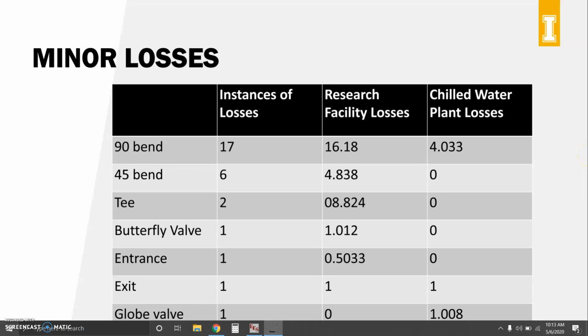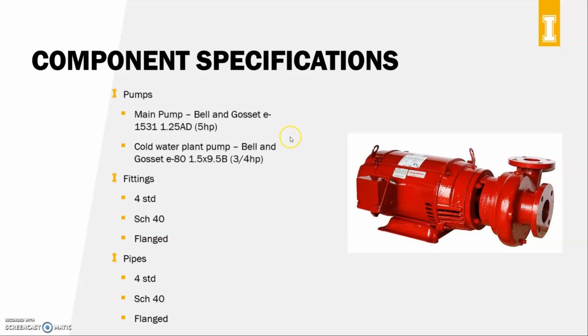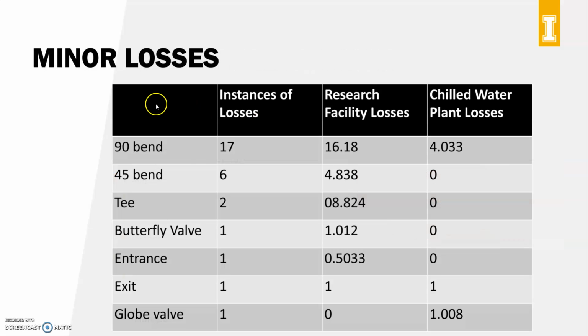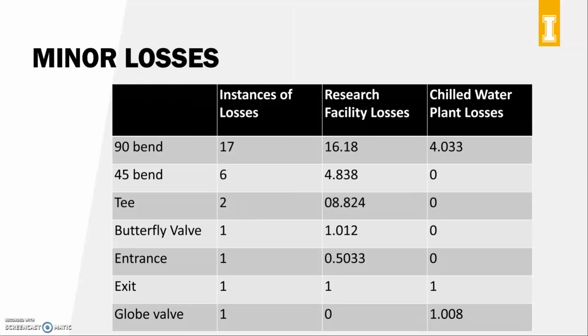Now, obviously, in a pipe system this large, we're going to have a good number of head losses throughout the system. So in this case, we have our minor losses, and we have approximately 17 90-degree bends, and this is also including our risers that we have to use at a few points. We have 6 45-degree bends. This is for the 2 points along the length, where you can see that there are slight S-curves, and then there are also 2 to account for the change in elevation.